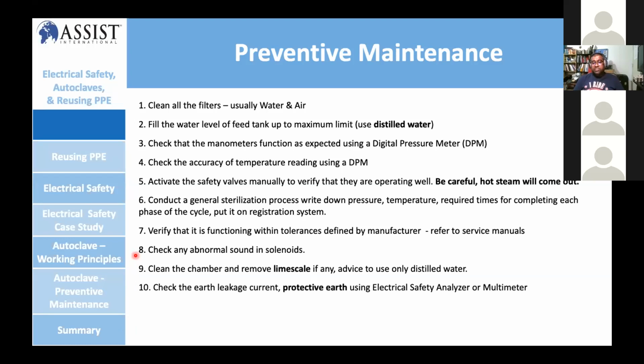Clean the chamber and remove lime scale, if any. Advise using only distilled water, which is very important. Check the earth leakage current and protective earth using an electrical safety analyzer or multimeter. You need to check whether your autoclave is grounded properly, because of safety issues. Remember, with bigger autoclaves the area is always wet, so you need to be careful. If the device is not grounded, anything can happen, and the chance of getting electrocuted is very high.